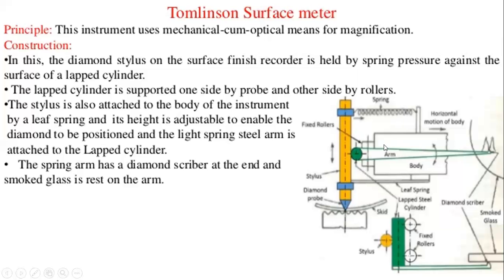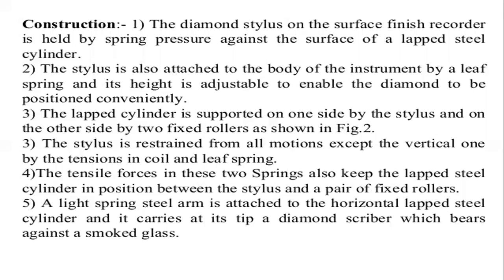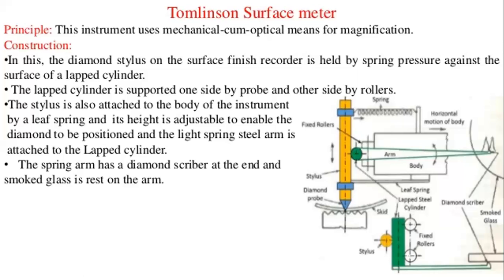So we go to the construction now. In this, the diamond stylus on the surface finish recorder is held by spring pressure against the surface of a lapped cylinder.